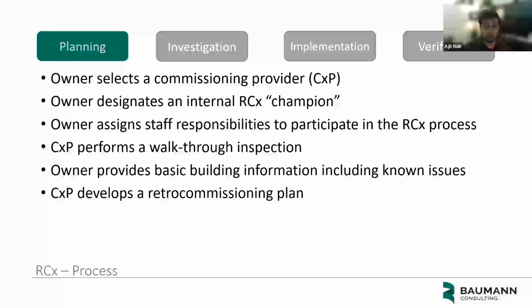The commissioning provider usually performs a walkthrough inspection. Usually this is after the commissioning provider is contracted, but sometimes it happens before. This isn't a detailed investigation, but just enough to understand what's happening in the building. The owner also provides basic building information, an equipment list, 2 years of utility bills, and a list of known issues. At this stage, the commissioning provider reviews all this information and looks for high-level warnings, right? Things like indications of simultaneous heating and cooling. Like, are we using the AC and the heat at the same time? Pumps that are running more often than they should. Air handling systems that are running in the middle of the night. Weird pressurization effects where it's hard to open or close the door. Piping that is hot or cold when it shouldn't be. Weird noises. Spaces that are bright, where the lights are on in closets when you don't expect them to be. Things like this that you can identify in just a few hours. This typical walkthrough is just like an audit. It takes just a couple of hours.